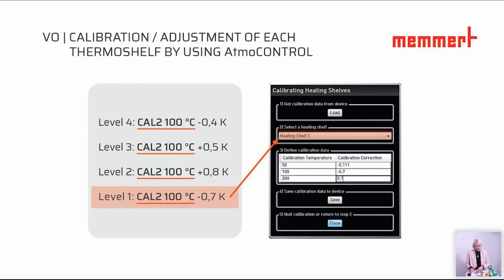And that means we can do here the calibration of the temperature, and this is for each of the plugs inside. So just consider when you do this calibration, always put the shelf in the direct position. Don't change it. But as mentioned, the most advantage is here that we can do the calibration of each shelf individually by using the AtmoCONTROL software. If you do the calibration, please kindly consider, of course, we cannot place any sensor in the chamber. We have to put the sensor on the tray directly. And for this reason, we also have special flat sensors.